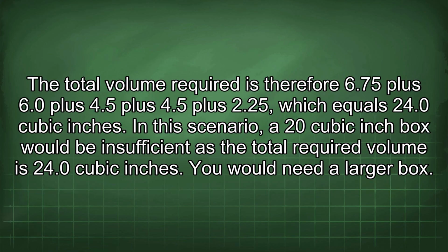The total volume required is therefore 6.75 plus 6.0 plus 4.5 plus 4.5 plus 2.25, which equals 24.0 cubic inches. In this scenario, a 20 cubic inch box would be insufficient, as the total required volume is 24.0 cubic inches. You would need a larger box.